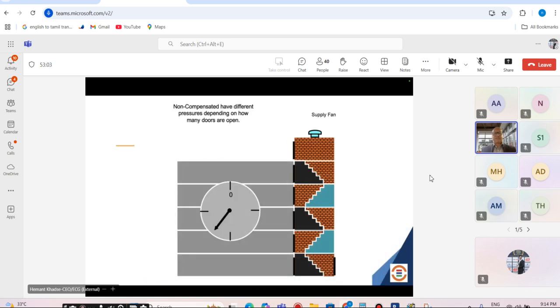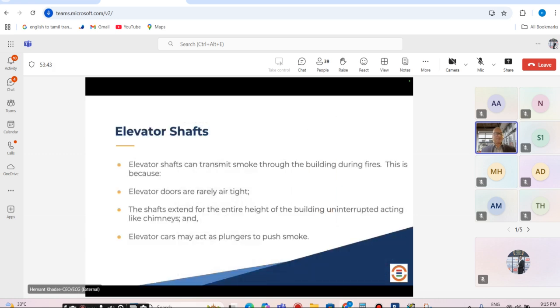So that's how it has the non-compensated or compensated engineered systems available, and you can have even single injection or multiple injection fans, again based on the occupancy that you have, based on the type of the building or height of the building that you may have, and you can actually define your pressurization systems so that the staircase, which is the most protected zone, becomes the smoke-free zone for evacuating people.